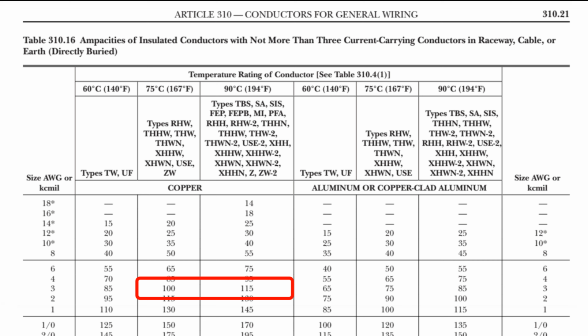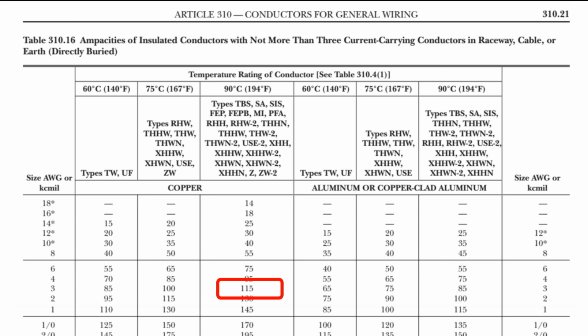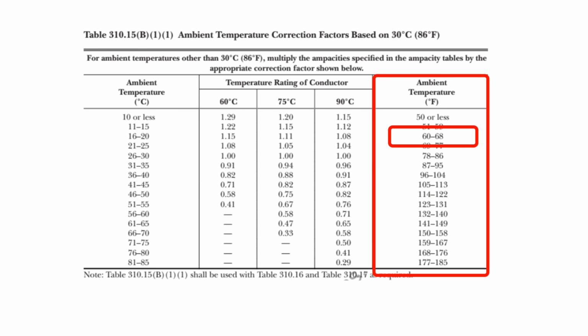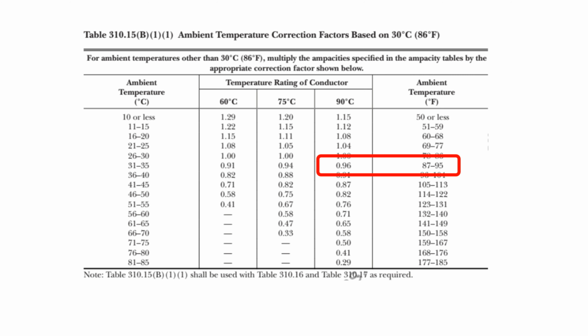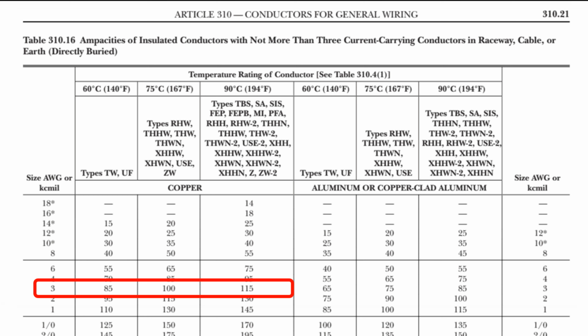Here's where we start to see why all that code review was worth it. For example, if we're wiring a circuit breaker with 75 degree terminations, we can apply the 90 degree column for conductors with a 90 degree rating. A conductor's temperature rating is required to be marked by the manufacturer. Our example conductors will be in the cellar where the ambient temperature is 86 degrees or less, and on the outside of the house where the ambient temperature can possibly go as high as 95 degrees Fahrenheit in the summer. So I'd be wise to apply a correction factor of 0.96 to the conductor's ampacity of 115 amps. 115 amps times 0.96 equals 110 amps. So we're good. Number 3 copper will meet the need, right?